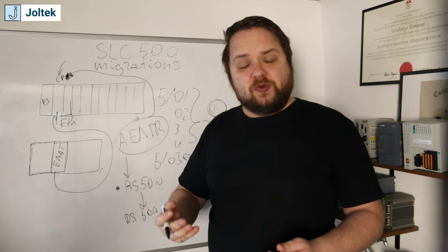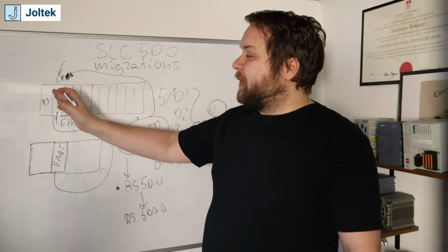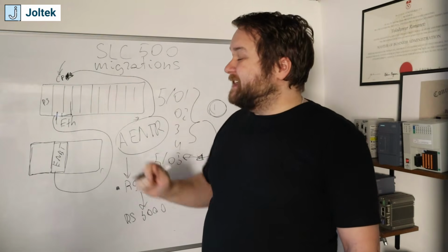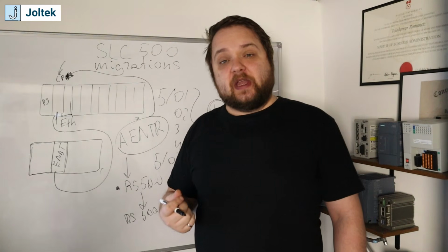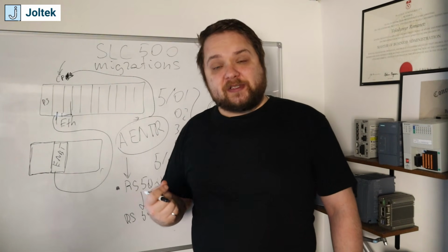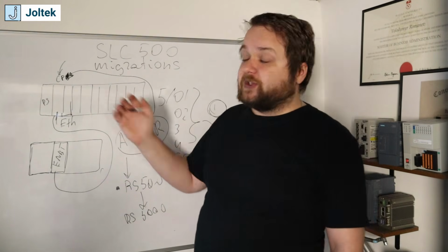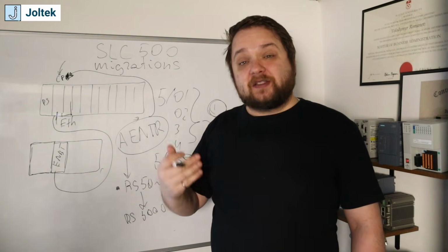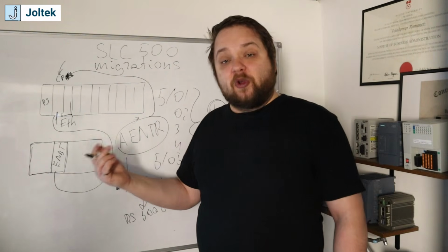So you probably take 2 hours, maybe 4 hours, maybe an entire day of downtime, where you swap out the PLC with this AENTR card. You make sure that everything is communicating as expected, and you always have a way to go back to the original setup, which is putting the PLC back, which should have a backed up program at that point. So this is going to be the second point of migration.